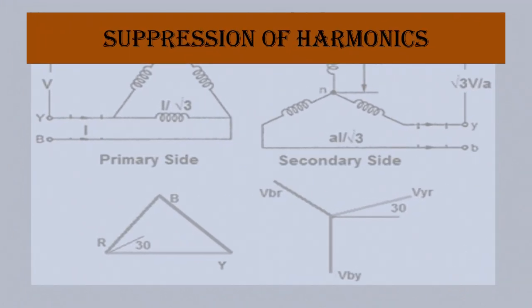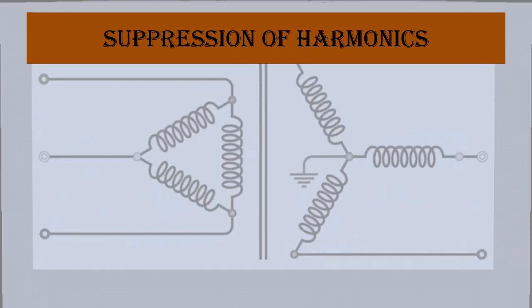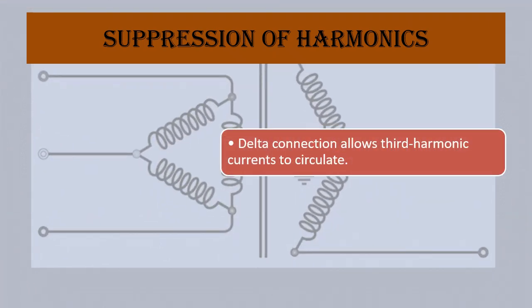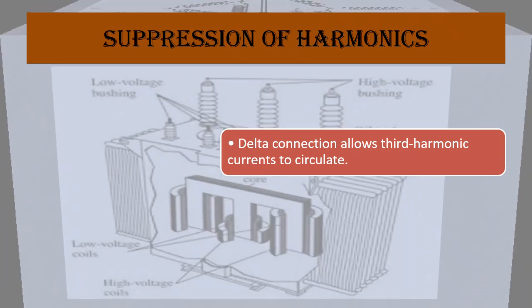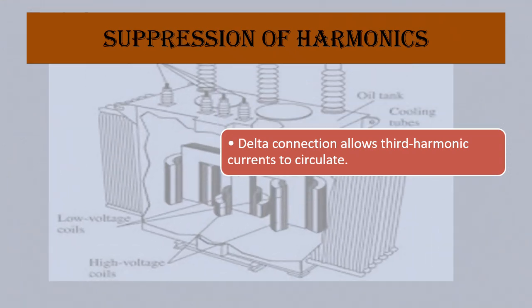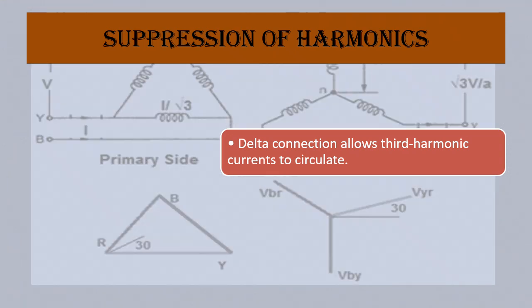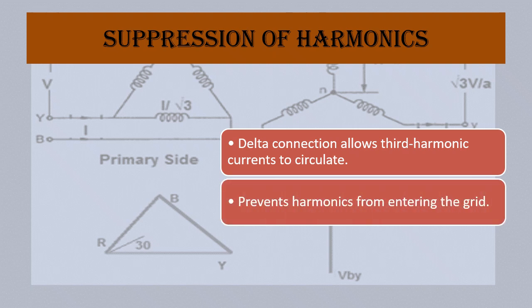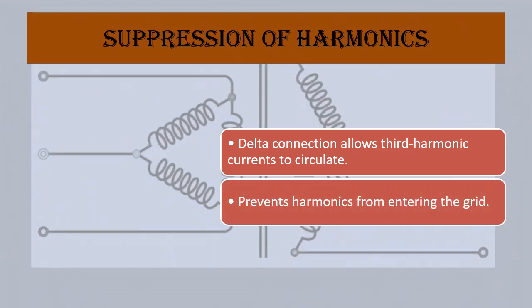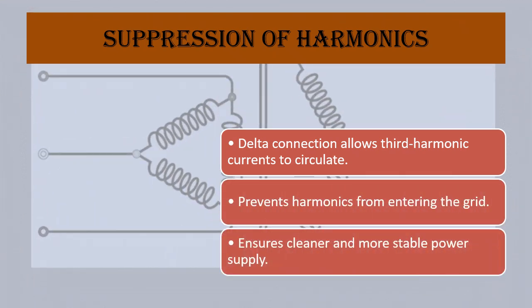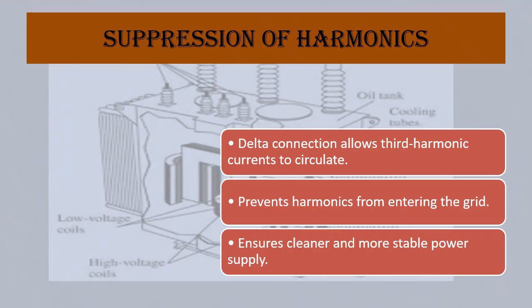Suppression of harmonics. Nonlinear loads create harmonic currents that can distort voltage waveforms and cause overheating. The delta connection on the primary provides a closed path for third harmonic currents to circulate, preventing them from being transmitted into the power grid. This results in a cleaner, more stable power supply.